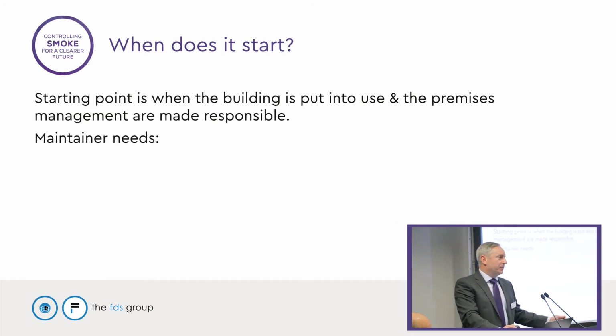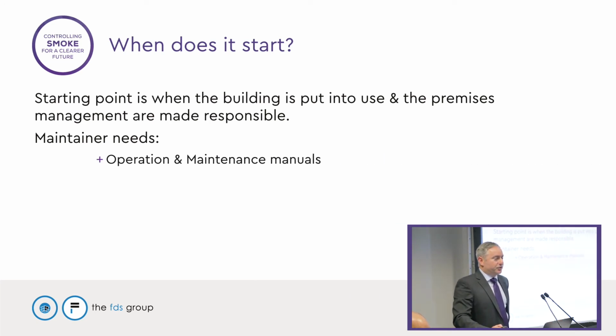So what sort of things do we need as maintainers? Well, if we walk into a building and we've installed the system, it's quite easy. We should have all the documentation we want. The challenge comes when somebody else installed a system and a maintainer turns up and says, what is it? So we need a range of information to help get the right result. We need O&M manuals. And they should be comprehensive with a full description of what the system is, what the system does. We need asset lists. If we walk along to a building that we didn't install, how many detectors in there? How many panels are in there? How many fans are in there? And sometimes people don't know, which is sometimes worrying.